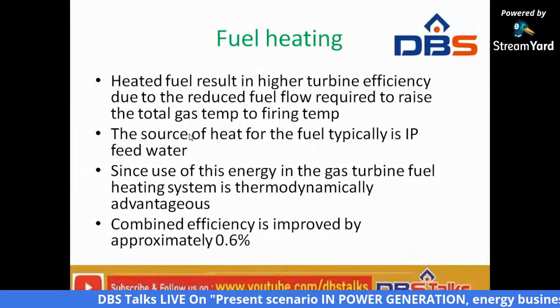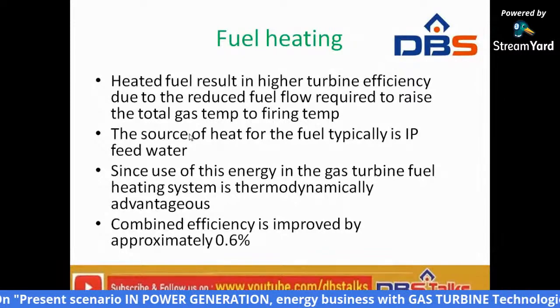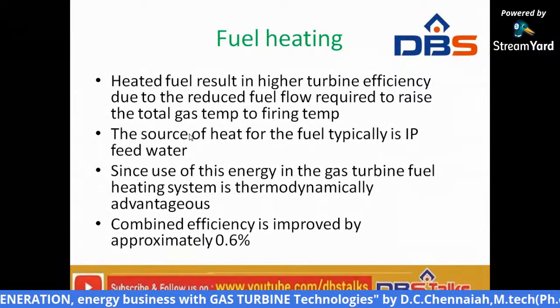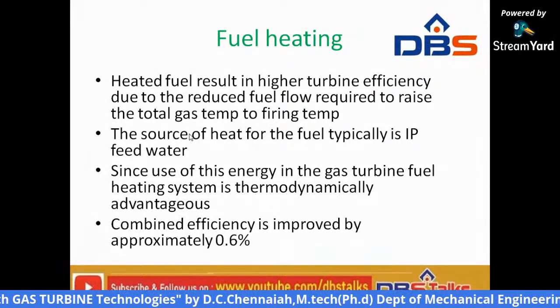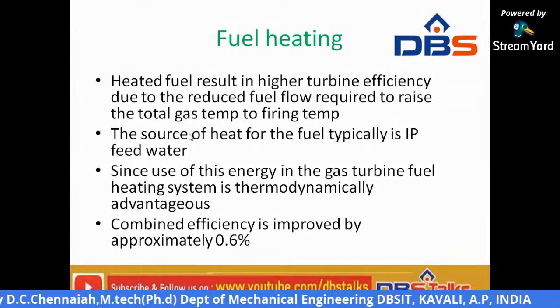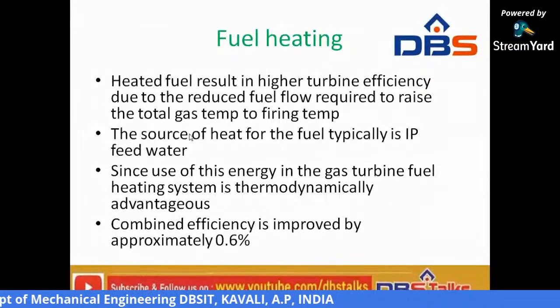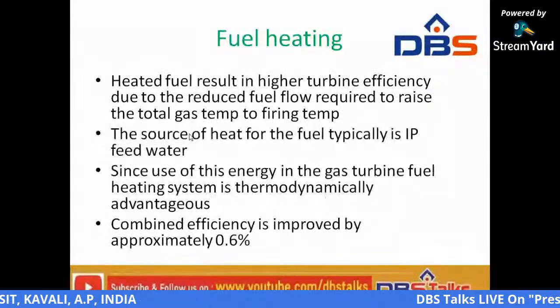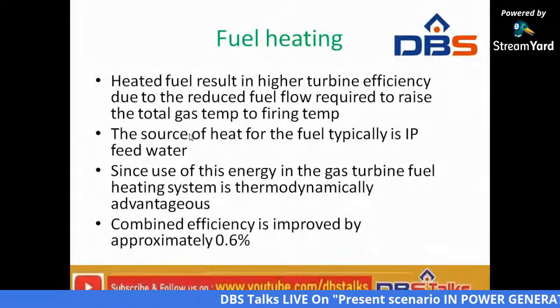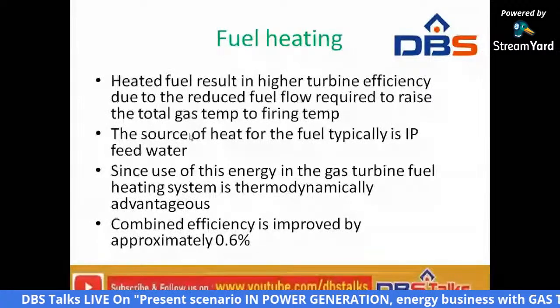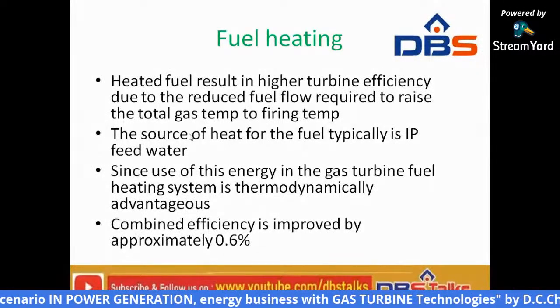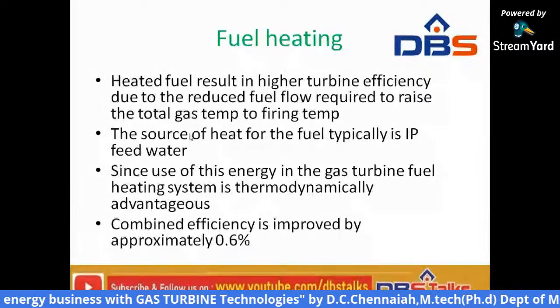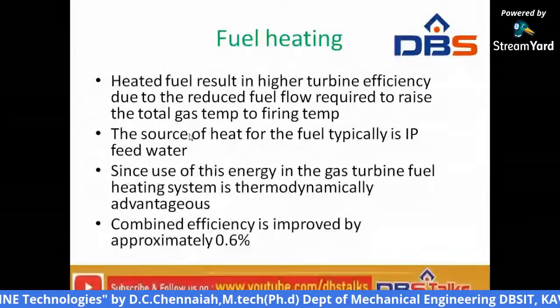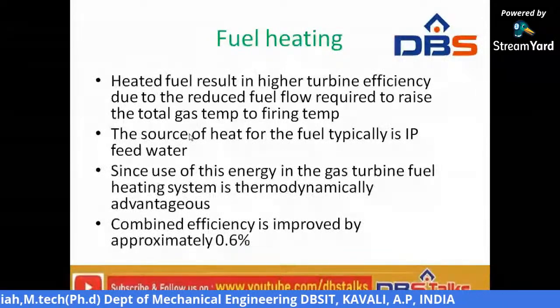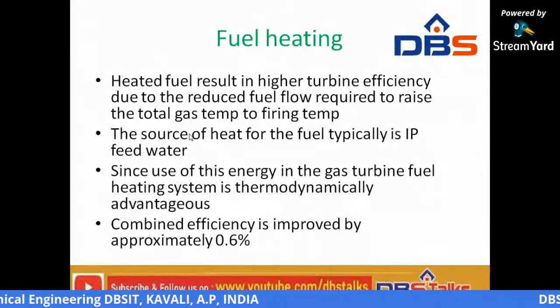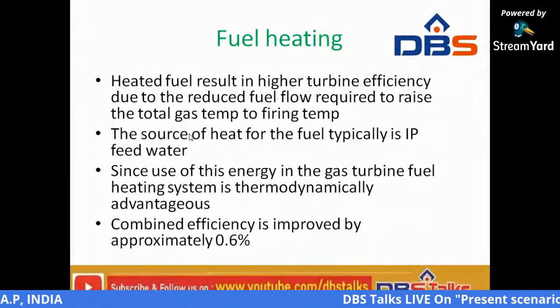Because of this, what happened? Combustion chamber temperature increases, best possible combustion takes place, and a high value of maximum possible generation of heat takes place, so that we can achieve the highest combustion efficiency. The source of heat for the fuel is typically the feed water. Use of this energy in the gas turbine fuel heating system is thermodynamically advantageous, because by using this heat from the feed water, by the method of fuel heating, we increase the combined efficiency by 0.6%.